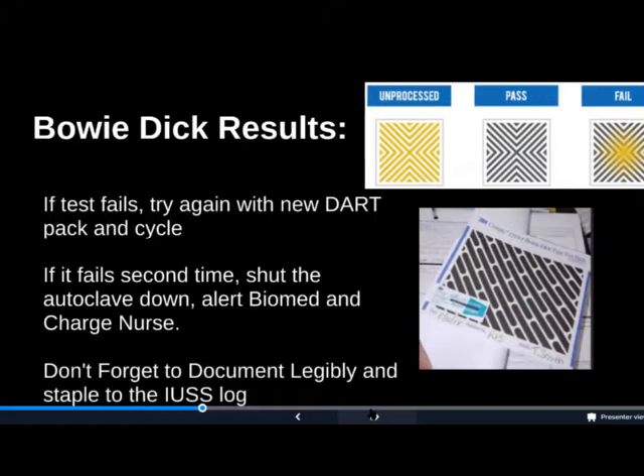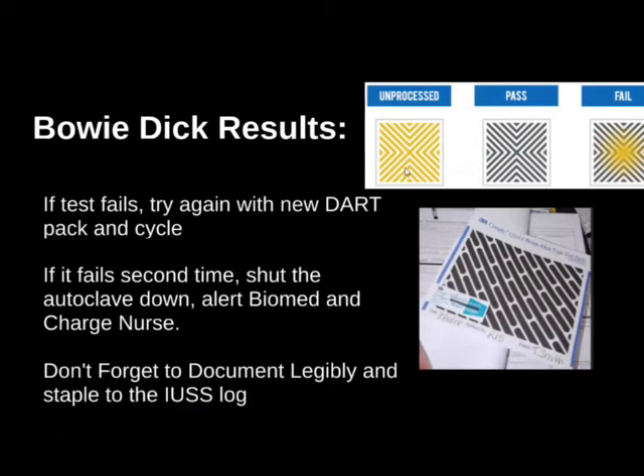So for the Bowie-Dick results, if the test fails, try it again with a new dart pack and cycle. Here above, you'll see the unprocessed form comes bright yellow. A pass is a full or uniform black color change. If you see any hints of lightness, or it's just not a uniform black, then that would be a fail. So you really want to make sure you're looking at these results. If you see yellow, you want to run it again with a new pack.